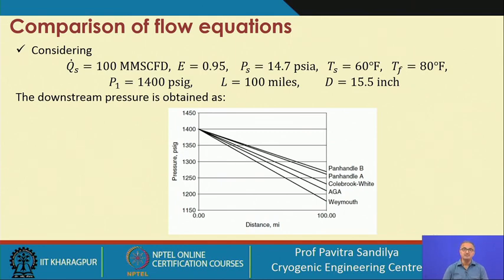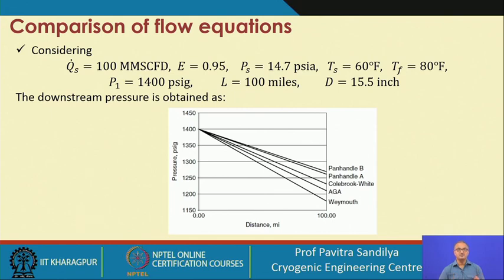This means Weymouth gives the maximum pressure drop and Panhandle B gives the minimum pressure drop. If we use the Weymouth equation, we need a compressor capable of handling very high pressure drops — so Weymouth gives a conservative estimate of pressure drop, requiring a higher capacity compressor with a higher pressure ratio.